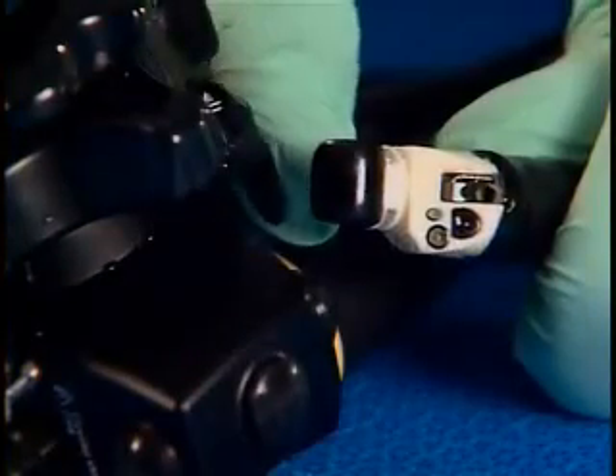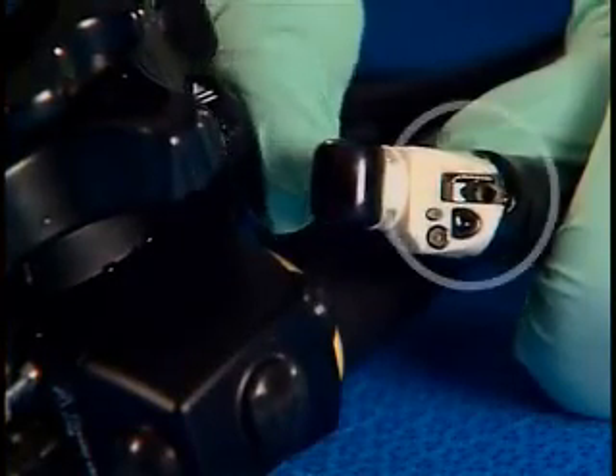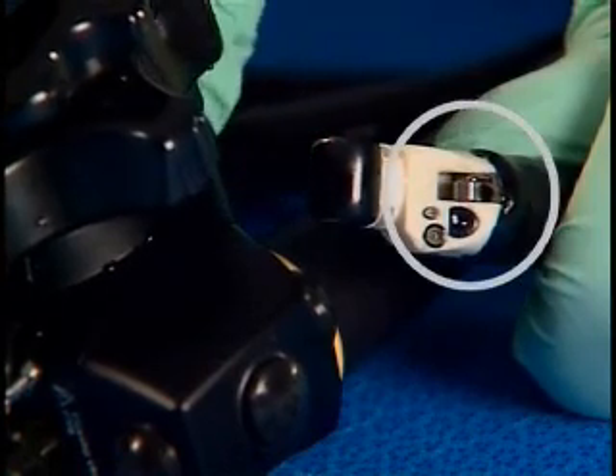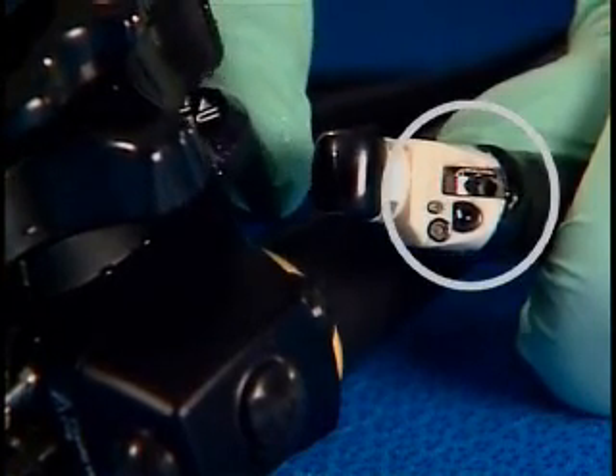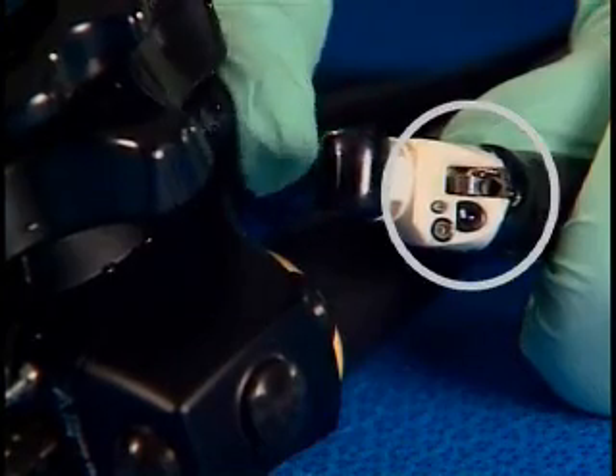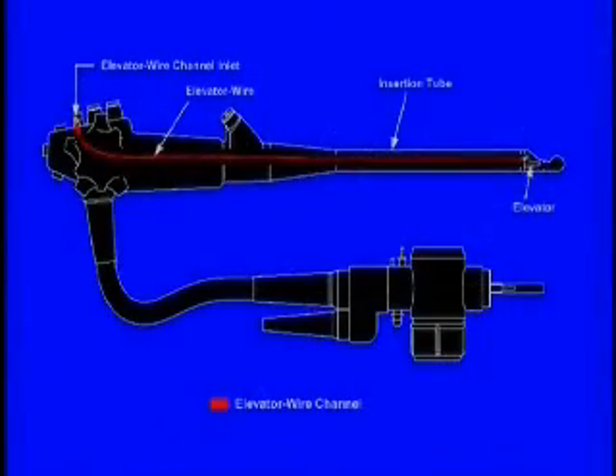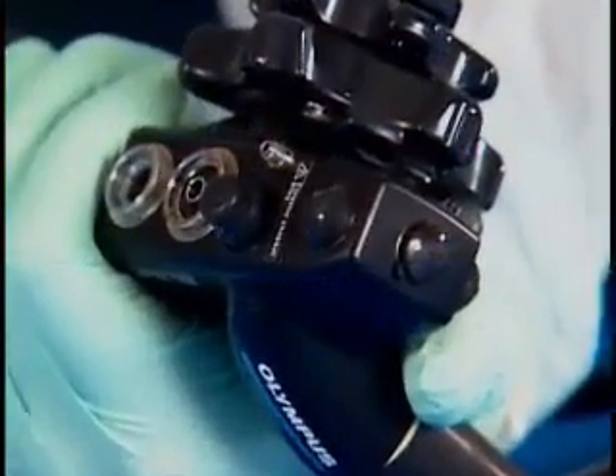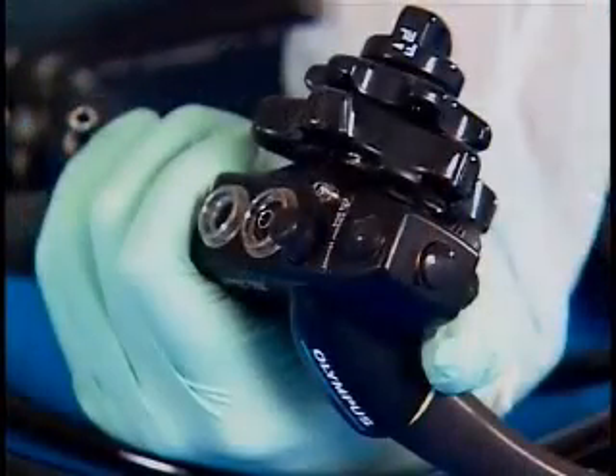In addition to these channels, if you are reprocessing a curvilinear array ultrasound endoscope, your endoscope has an elevator wire channel. CLA ultrasound endoscopes contain a channel with a metal part called an elevator that is used to manipulate accessories which have been passed through the instrument channel. The wire that controls the movement of this elevator runs in a channel called the elevator wire channel. You will find a port to access this channel on the control section of all CLA ultrasound scopes.